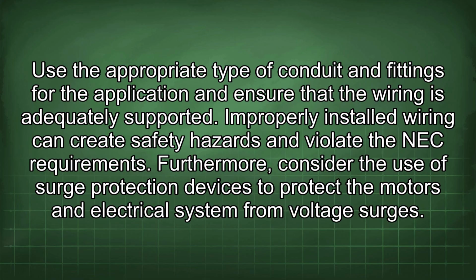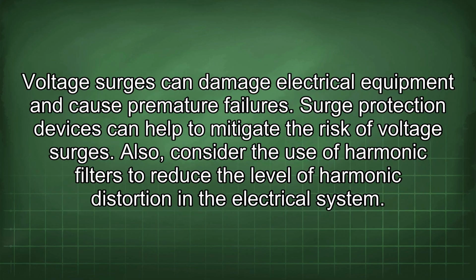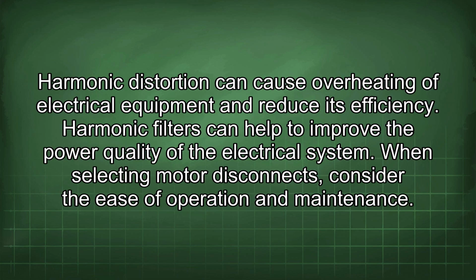Furthermore, consider the use of surge protection devices to protect the motors and electrical system from voltage surges. Voltage surges can damage electrical equipment and cause premature failures. Surge protection devices can help to mitigate the risk of voltage surges. Also, consider the use of harmonic filters to reduce the level of harmonic distortion in the electrical system. Harmonic distortion can cause overheating of electrical equipment and reduce its efficiency. Harmonic filters can help to improve the power quality of the electrical system.